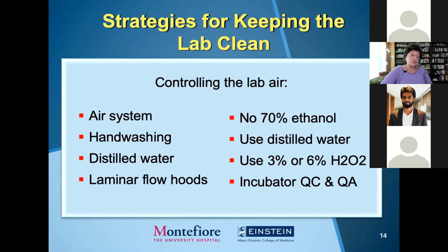The air handling system should function according to set parameters, and periodic testing for VOCs in the lab air should be implemented. Air filtration systems should ideally be installed at the time of lab construction. Less ideally, labs may be retrofitted and/or floor units containing fans and an air filter may be placed in the lab. Most modern-day labs have installed into their air systems some or all of the following filters: high efficiency particulate absorption, which is HEPA filters, carbon filters, or carbon potassium permanganate filters.